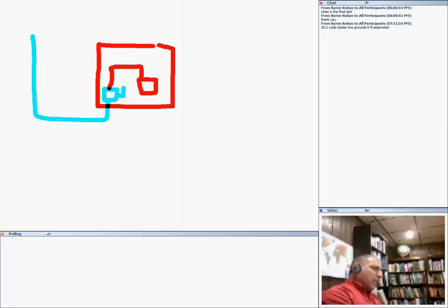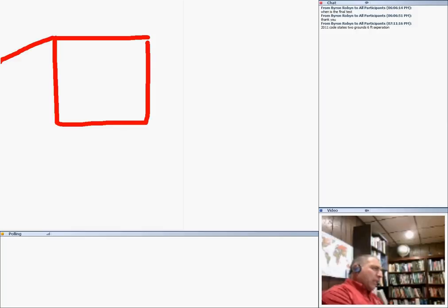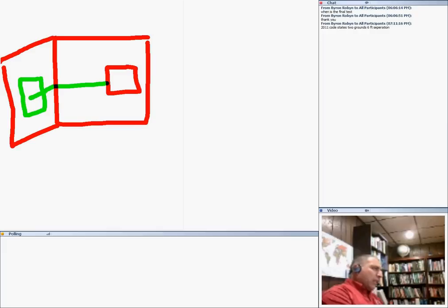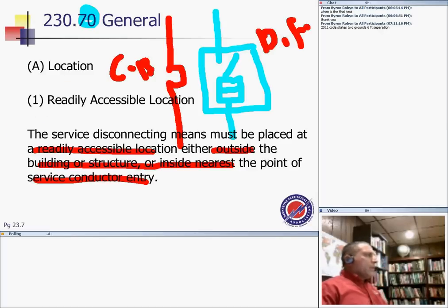Inspector guys, if you enter from one wall, they want the service disconnect and the main service disconnect to be on the same wall. If your panel is right here, you can't just bring your feeders from right in here. How am I going to do that one? You can't bring your feeder from here, go through here, and feed your panel. So you have to put your panel right in here as you enter, on the same wall. Any question, guys, about this? As close to the service entrance conductors as close to entering as practical.